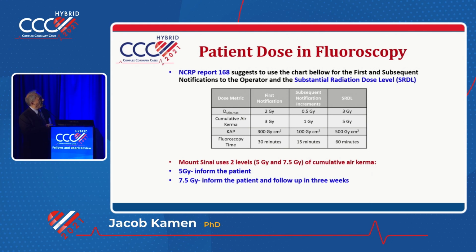Now here, NCRP 168 is a guideline. I think you should get a copy of it because this is your lifetime job. So get a copy of it and look at what it says. NCRP says you could take any of these, let's say skin dose, air kerma, all of these. But fluoroscopy time is the easiest one to follow.